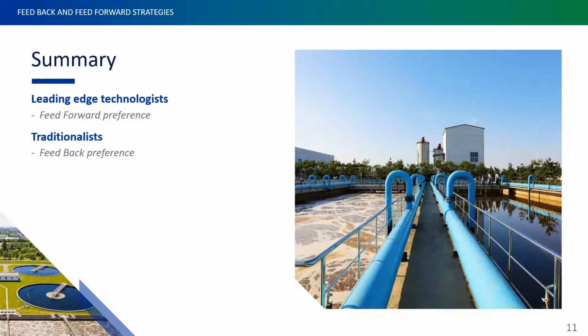I'm a very strong proponent of feed forward plant flow pacing. Think about the feedback loop: everything is over-designed and operating in maximum mode, and rarely does a plant operate in peak conditions outside of the morning or afternoon peak. So in the middle of the day, there's no reason to run copious horsepower of aeration, pumps, and recirculation. That's why it's important to have flexibility in monitoring, to understand the pulse of your plant so you can flow pace it based on loadings and flow conditions.